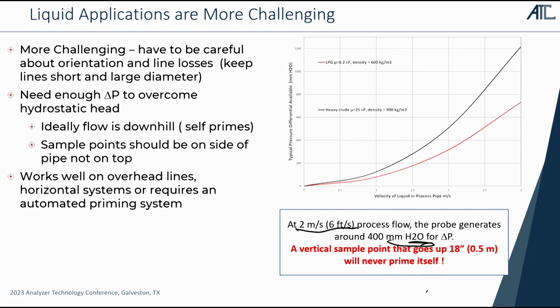We can't get over a lot of hydrostatic head. If you talk to people who put scoop probes in or flow impact probes on liquids applications, they'll say, we tried it and it didn't work. And it doesn't work if you don't install it properly. If you put that probe in vertically on the top of the pipe, the differential pressure has to overcome the hydrostatic head. If the line runs up towards the analyzer, it will never prime. To do these installations, we have to try to make sure that the probe is installed on the side of the pipe, and ideally the analyzer is lower than it, so we have a downhill run for liquids that will self-prime. Otherwise, we've got to put a mechanism for priming in.